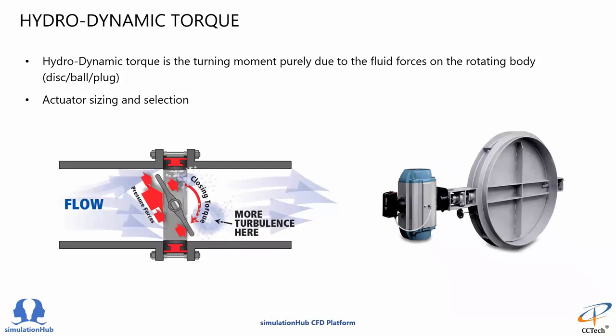Now hydrodynamic torque is the second important parameter under flow performance studies. Hydrodynamic torque is the amount of turning moment experienced by the shaft purely due to the forces of the fluid on the rotating body of the valve. These unbalanced forces induce a torque in the shaft. This torque plays an important role in selecting and sizing of the actuator.